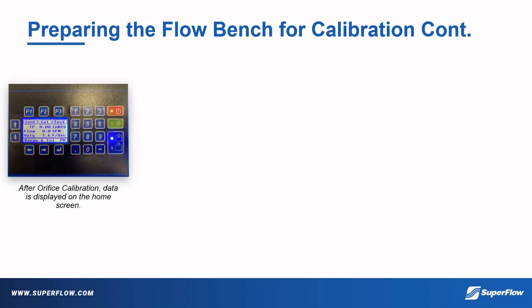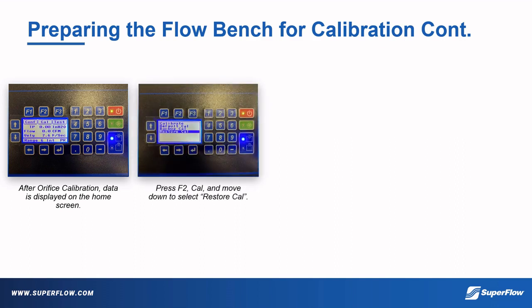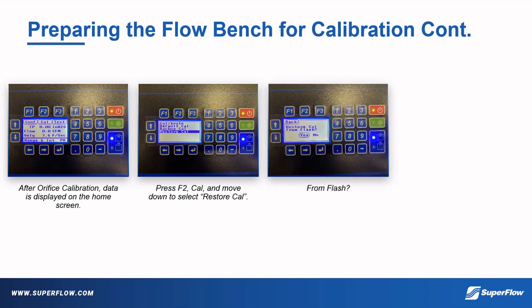After orifice calibration, you'll see data displayed on the home screen. TP, test pressure, flow rate, and velocity are shown. Press F2 and go down to Restore Cal. When asked to restore cal from flash, select Yes.